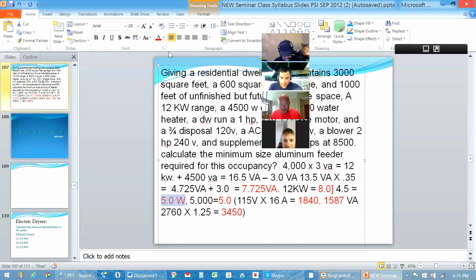If you look in your code book at 220.51, which is the very bottom left-hand corner of page 70, 220.51 tells you that fixed electric space heating is going to be calculated at 100%, so we're just going to take 100% of the fixed electric space heating. But if you also look at 220.60, which is on the right-hand side of page 71, non-coincident loads that don't operate at the same time, you can take the larger of the 2 loads if you have a situation like that. In this case, a central heating and air conditioning unit like this would either run the air conditioning during the summertime or run the heating during the wintertime, but they wouldn't run simultaneously, so they're non-coincident loads. We're going to omit the smaller of the 2.